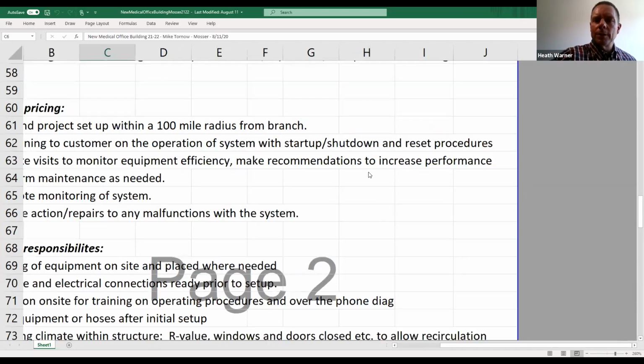Fuel cost, I'm gonna shrink a little bit. Fuel cost predictions are between $639 a month and $1,668 a month to operate a hydronic system. That's for temperatures between 37 degrees and 0 degrees. When you start figuring out costs like that, law of averages takes over, because what winter in the world is going to be all 37 degrees and what winter is going to be all 0 degrees? So you take the average, you're looking at about $1,154 a month predictions to heat that 30,000 square foot building.